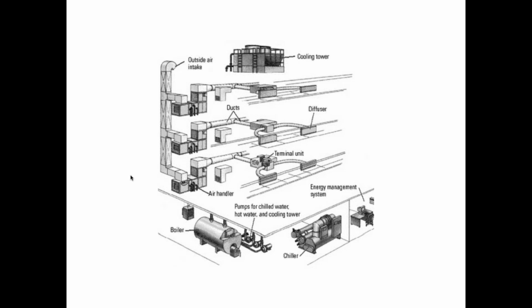More modern buildings take that ductwork, that air that's being distributed around the building, and send it to a terminal unit, or what they call a, I'm having a senior moment here. I'll just call it a terminal unit, a variable air volume box, right? That terminal unit may serve only one diffuser, or two or three diffusers, maybe two offices side by side.